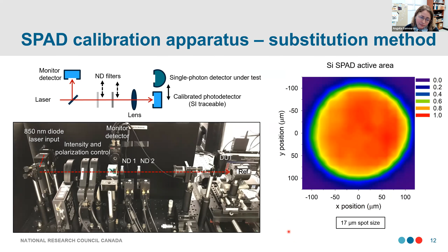At the National Institute of Standards and Technology, the US National Metrology Institute, they have a similar calibration system to us, but it's mostly fiber-based. So this was built by Thomas Gerrits at NIST. And so they also use a fiber-coupled laser, but they use variable fiber attenuators instead of ND filters to reduce the laser power in this case. They can also switch between a fiber-coupled scheme, which you can see here, and a free space scheme in their setup.